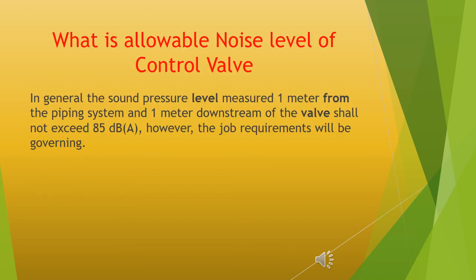What is the allowable noise level of a control valve? In general, the sound pressure level measured one meter from the piping system and one meter downstream of the valve shall not exceed 85 dB(A). However, the job requirements will be governing.